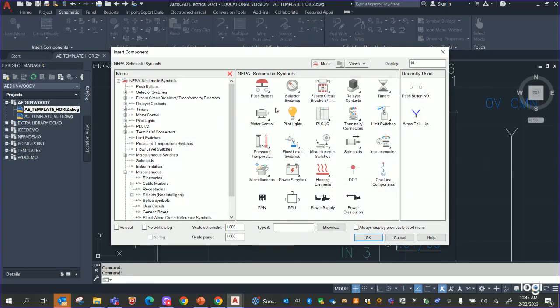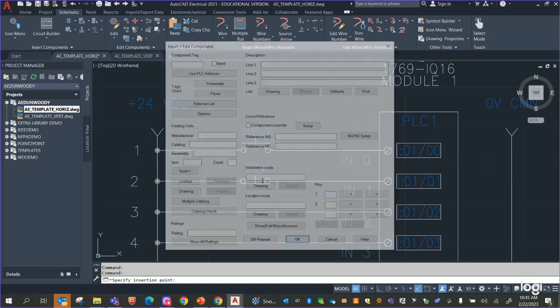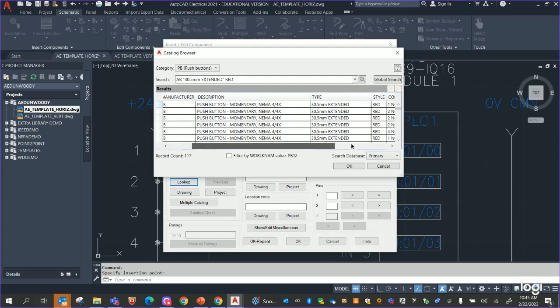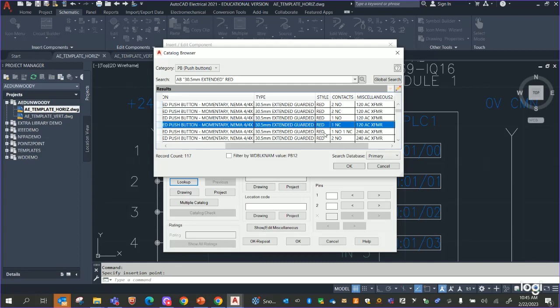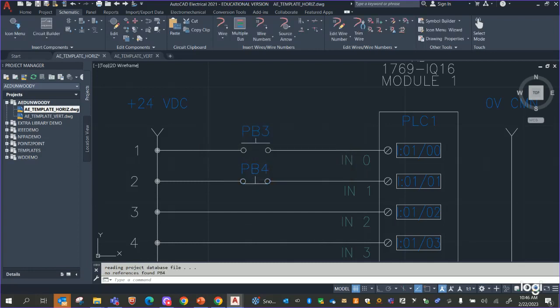Let's do another one. I'll go into the icon menu and grab a normally closed push button this time and place it on that rung. I'll look up the data — looking for something with a normally closed contact. Here's one that looks good: normally closed, same 30.5 millimeter size, rated at 120 volts AC. I'll hit OK. Now you'll get this dialog every once in a while asking if you'd like to map this to the catalog number. That means every time you drop a normally closed push button, it would automatically map to that catalog number. I prefer not to map it — I'd rather select it manually when needed.